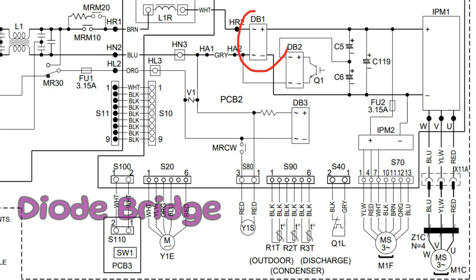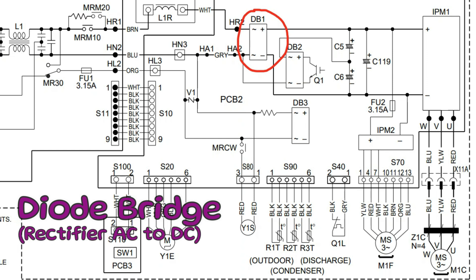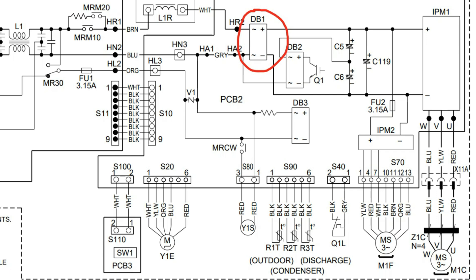Moving on, we come to a diode bridge — which is a rectifier. It converts an alternating current signal to a DC signal, and the reason we do this is because a DC signal is a little more stable and we have more control over it. You're going to have different arrangements when it comes to diode bridges in these units. Sometimes you might have one diode bridge feeding one power module for the compressor and another feeding a separate power module for the condenser fan motor, since these motors use different voltages. Sometimes you might have diode bridges in series together, which adds another layer of stability and reduces interference.